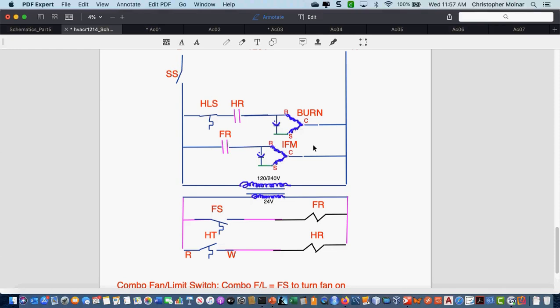There's a bigger reason. What happens on a cold winter day to the inside of a house if there's no heat whatsoever? Freezing pipes. Freezing pipes and property damage. So even if I don't have a blower motor that's operational, that furnace that's getting hot sitting in the basement while someone's out on their winter break to Vermont or whatever it is, that furnace sitting in that basement is going to put off a little bit of heat, probably enough heat to not freeze the pipes.